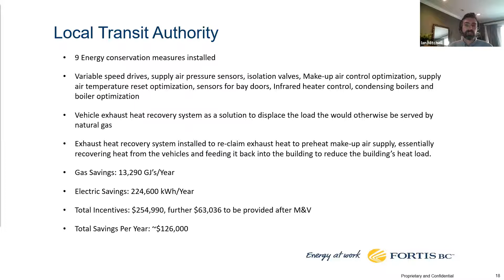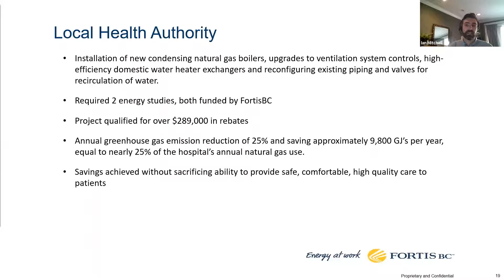The next example I wasn't personally involved with—it was one of my colleagues—but it involved upgrading the heating plant, putting in condensing boilers, upgrading the ventilation system, and reconfiguring piping and valves. This one actually had two energy studies. Typically we fund an ASHRAE level 2 study, but sometimes the consultant on site sees a need to do a deeper dive into a particular area or system, like a more detailed ASHRAE level 3, and there can be funding for that too, either within the same program or leading into another custom program. This project had quite significant savings—about a 25% reduction in gas emissions, just shy of 10,000 GJs a year—and they received an incentive just shy of $300,000. A very successful project.